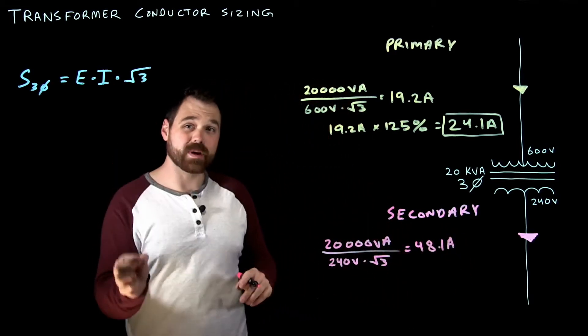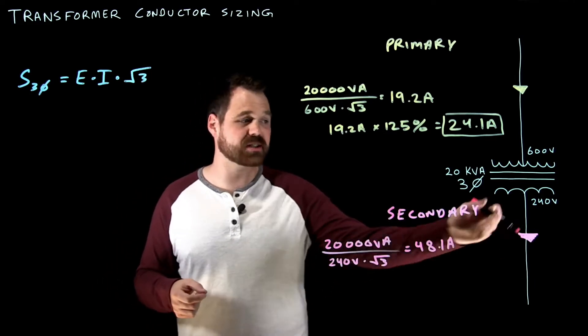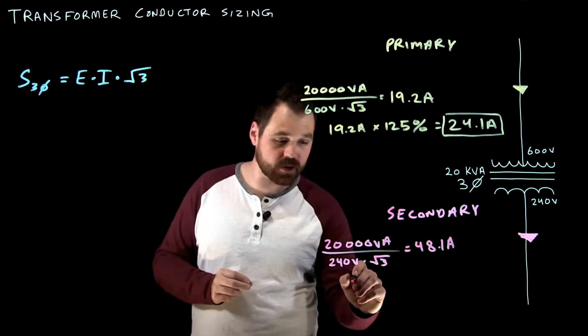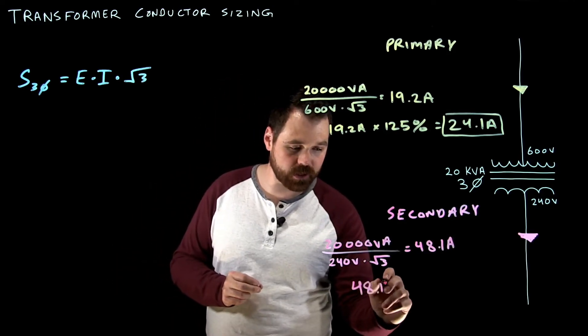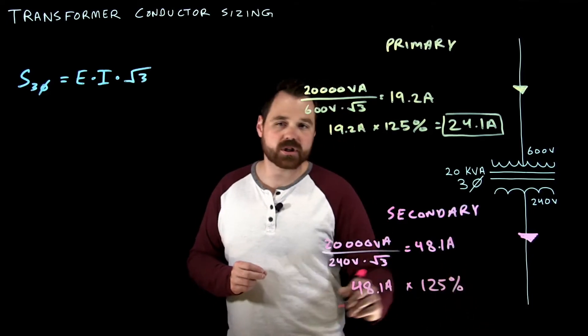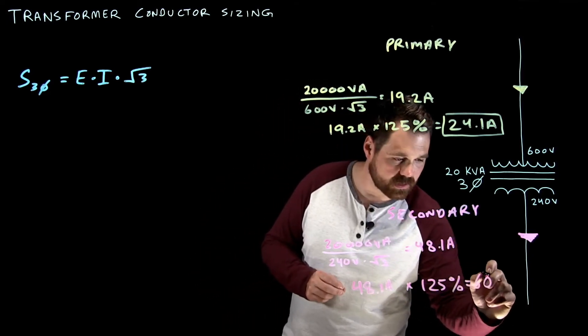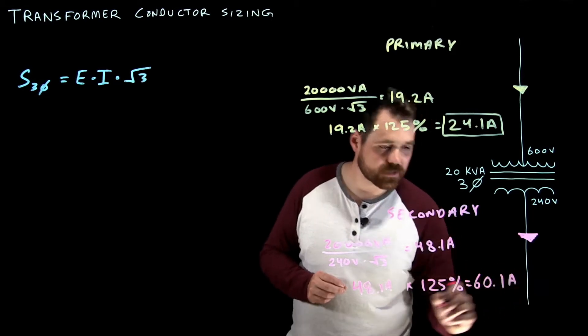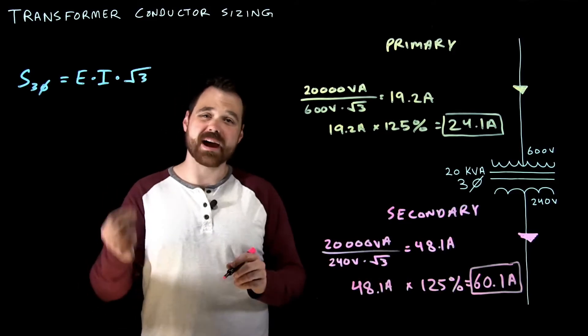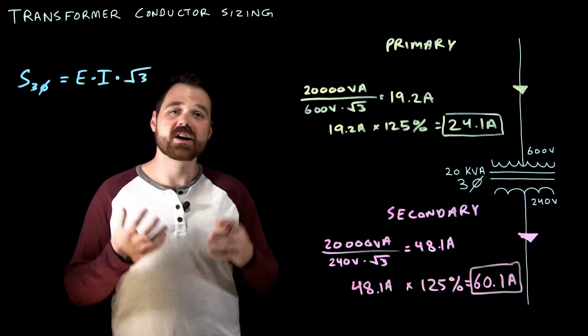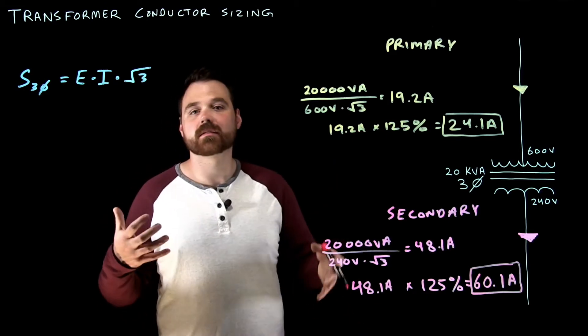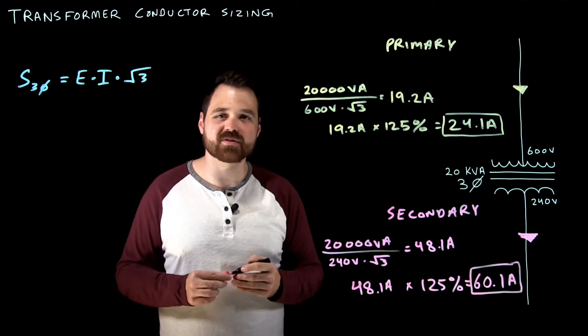And that is going to give us 48.1 amps. Now that's our rated current, that's the rated current of the secondary of the transformer. But we need to take that number 48.1 amps, and multiply it by 125%, which gives us 60.1 amps. Now this number, that is the required ampacity or the minimum ampacity of our conductor in order to safely be connected to the secondary of that transformer.